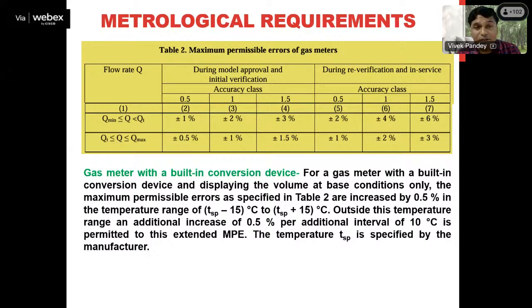You can see here that for the tolerances specified in the table, another statement is given just below the table, that suppose a specified temperature for a gas meter by a manufacturer is say 30 degrees Celsius. Okay, he has specified that the specified temperature is 30 degrees Celsius for a gas meter.